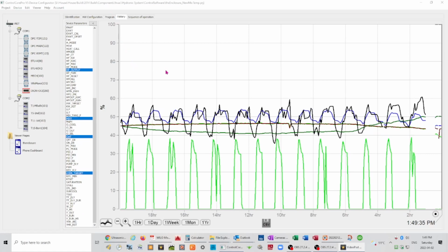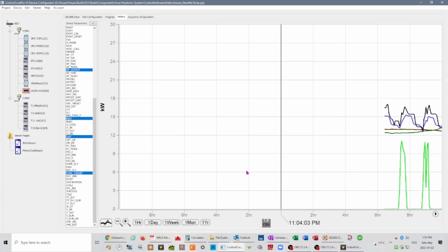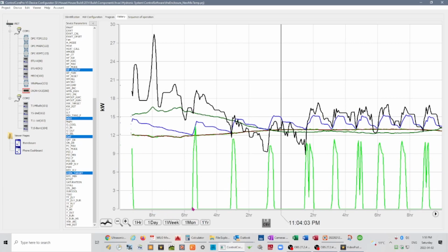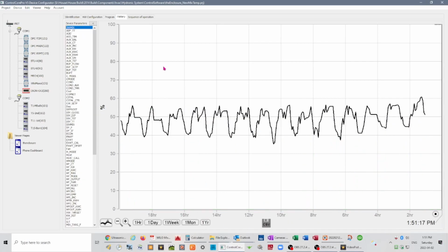What I specifically want to show you is, let's take out, this is the cycles of the heat pump. So you can see here, it's fairly cold today. It's 8 degrees and it's not sunny, so it's a full 8 degrees. I'm not getting any solar heat gain. So at 6:55 a.m. it turned off. The next one was at 7:51 a.m. So 6:55, 7:55, an hour basically on that cycle. During the day when it was warmer, at 5:54 it turned off, turned back on at 7:56. So you can see a couple of hours there.